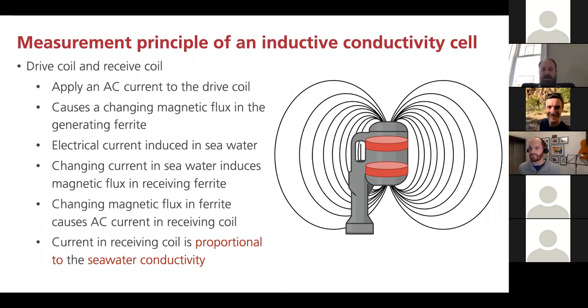Each of those ferrites has coils wound around them. And so we apply an AC current to the drive coil. No transformer works at DC, so you must apply an AC current. That current drives a flux in the ferrite. The ferrite, in turn, will induce an electrical current in any conductor that passes through the center. And in the PowerPoint here, we say it's induced in the seawater, but actually it would also be induced in a wire loop.